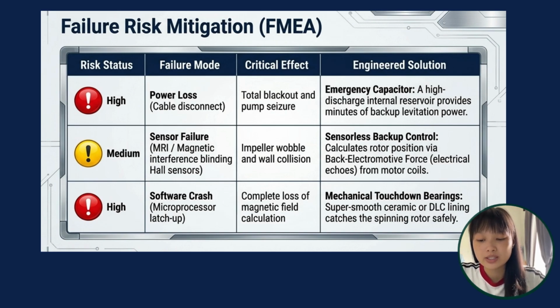The last risk is the controller software crash. The maglev system is controlled by a high-speed microprocessor. Like any computer, the software may crash. If the software stops calculating the magnetic adjustment, the impeller will immediately fall out of its floating position. Therefore, we need mechanical touchdown bearings as our solution.